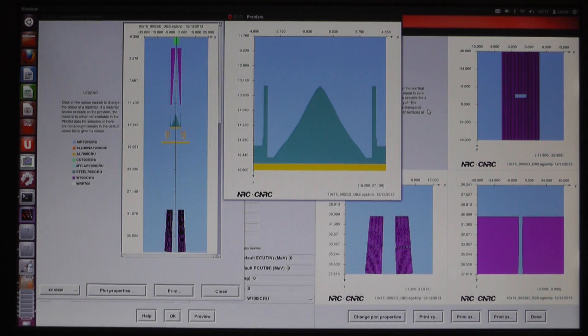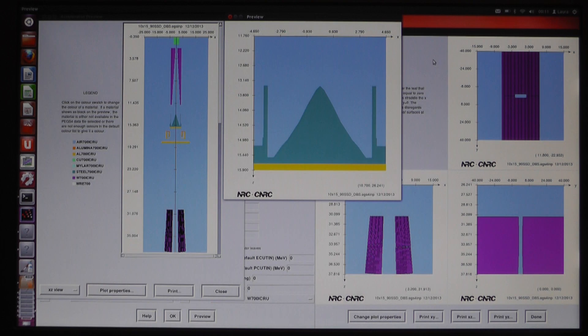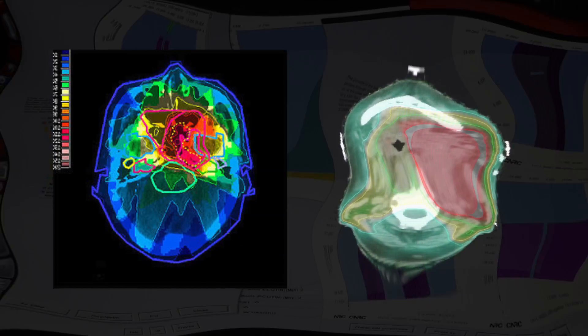To do this, I've created a virtual model of the LINAC that can calculate dose more accurately than the treatment planning system, but takes a long time. I treat the virtual model as my gold standard and compare to the treatment planning system calculated doses.